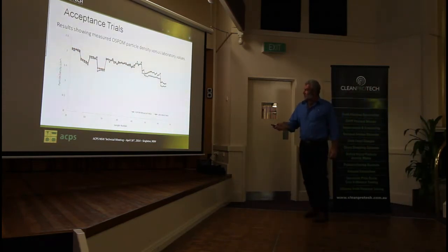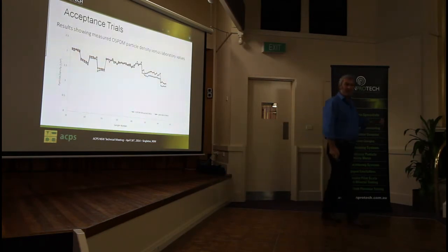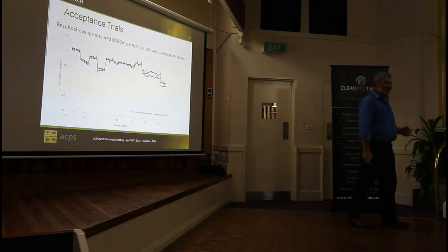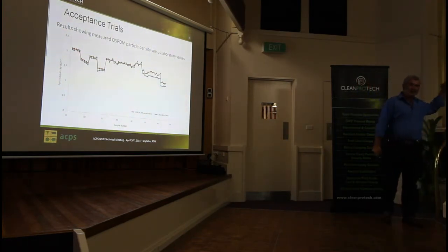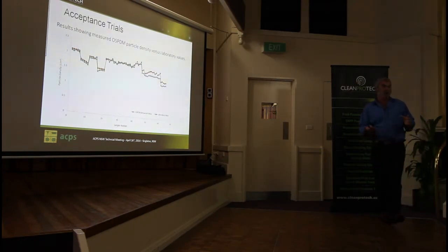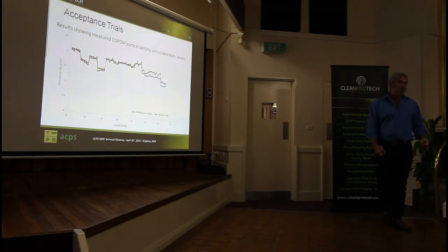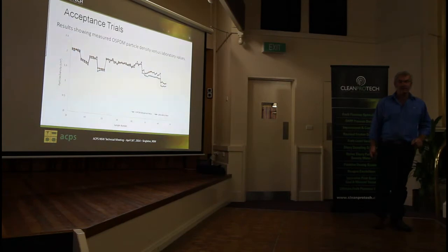Here we did get a bit of a divergence, but we actually found that just at that point, maintenance, without telling us, or even telling the Bloomfield process staff, had changed the upstream system before our sample points and had changed essentially our calibration, our spear points, greatly reducing the height of the liquid within there.